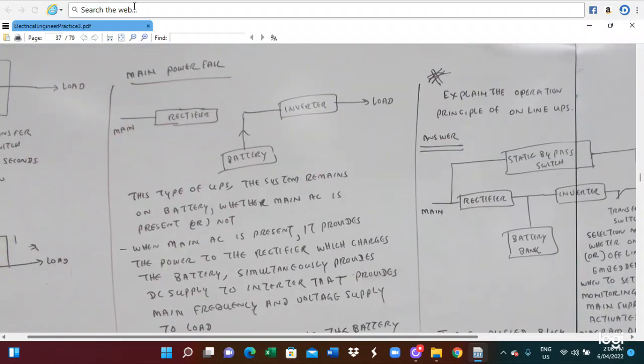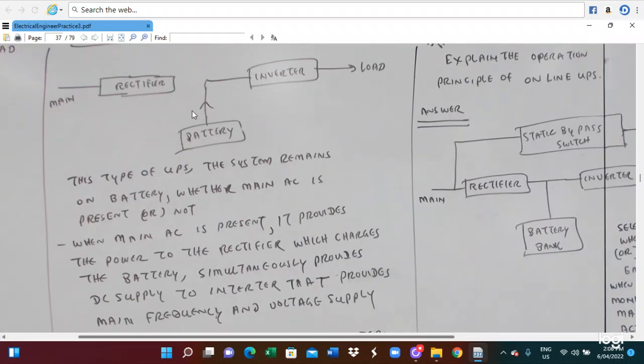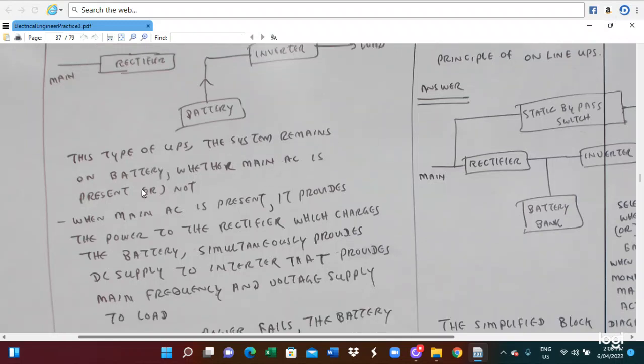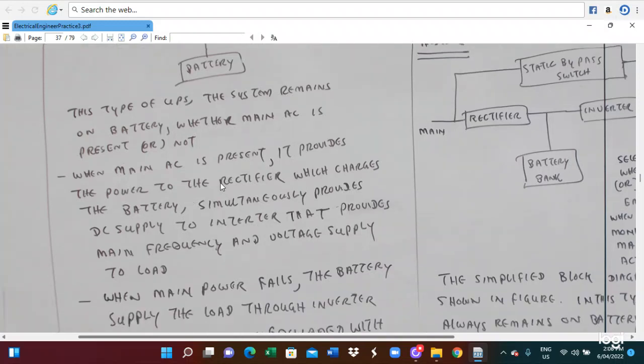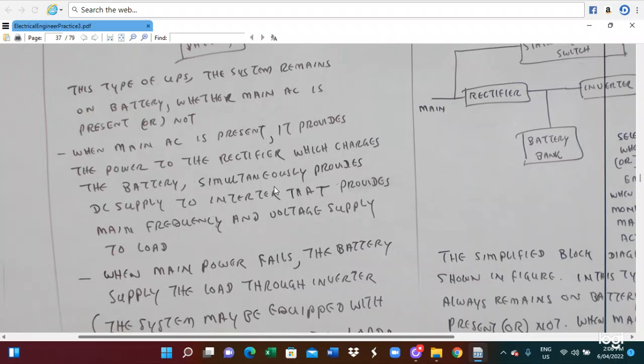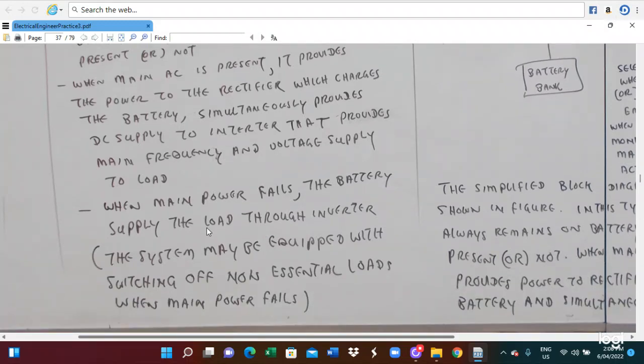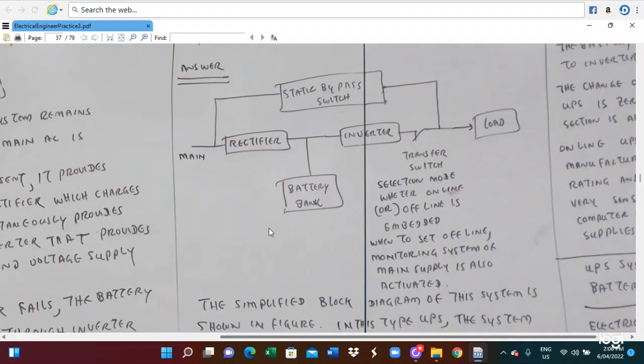So the main power failed. When the main power failed, the battery is supplying the inverter, which is connected to the load. This type of UPS system remains on the battery whether the main AC is present or not. When the main AC is present, it provides power to the rectifier, which charges the battery and simultaneously provides the DC supply to the inverter, which provides the main frequency and voltage supply to the load. When the main power fails, the battery supplies the load through the inverter. The system may be equipped with switching of non-essential loads when the main power fails. So this is for the connection.